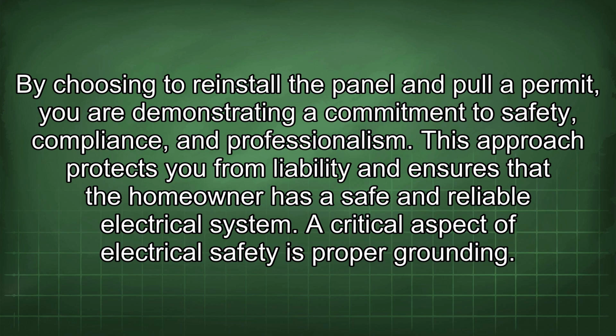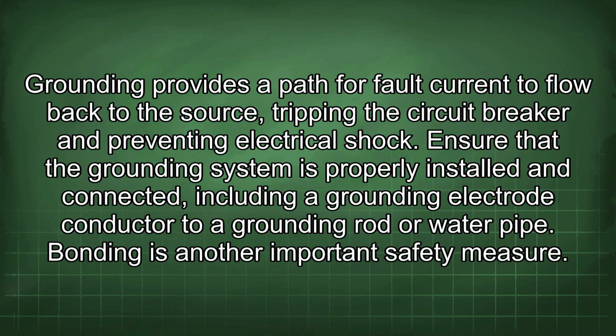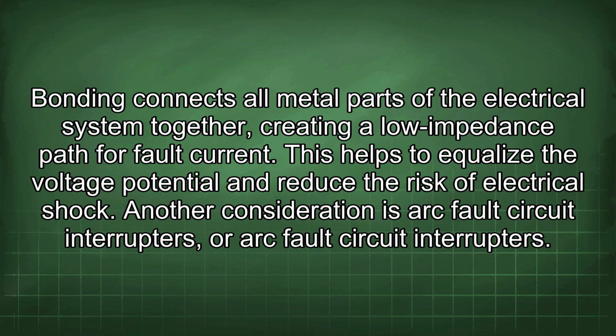A critical aspect of electrical safety is proper grounding. Grounding provides a path for fault current to flow back to the source, tripping the circuit breaker and preventing electrical shock. Ensure that the grounding system is properly installed and connected, including a grounding electrode conductor to a grounding rod or water pipe. Bonding is another important safety measure. Bonding connects all metal parts of the electrical system together, creating a low impedance path for fault current. This helps to equalize the voltage potential and reduce the risk of electrical shock.